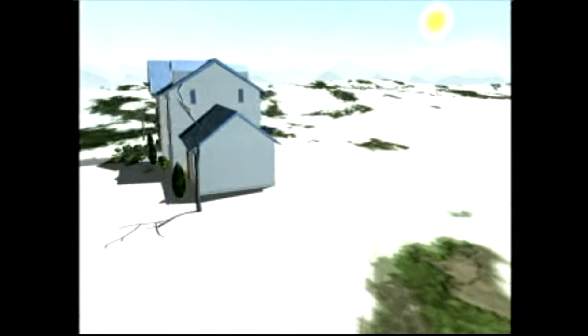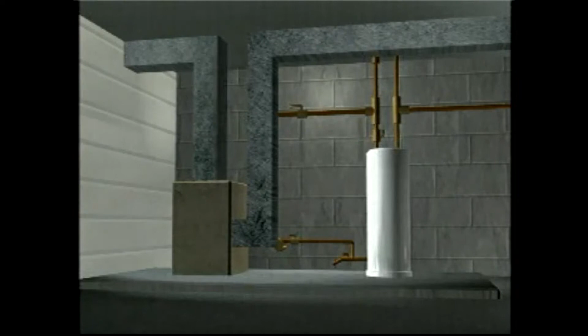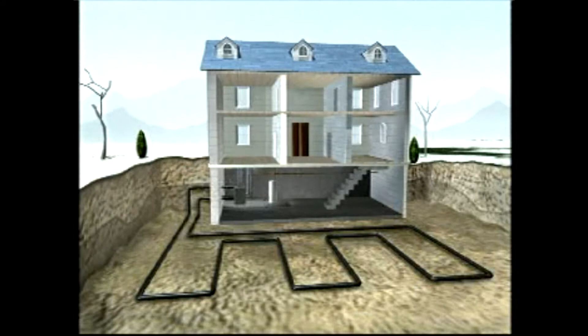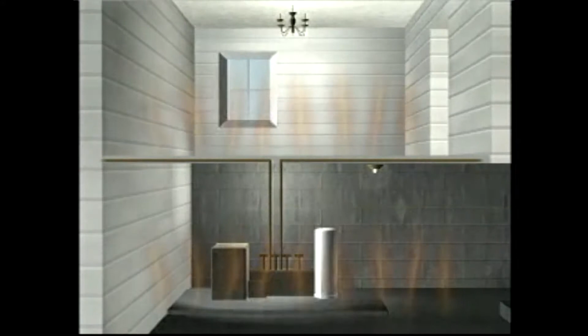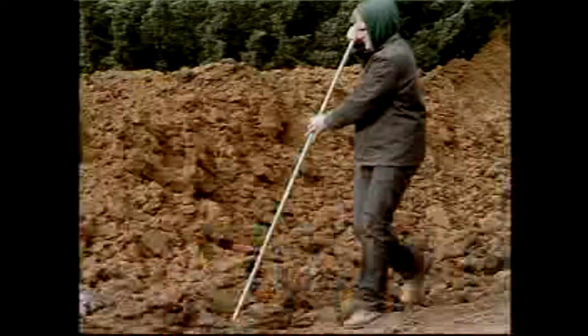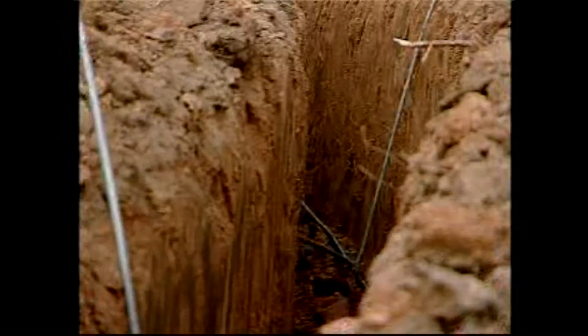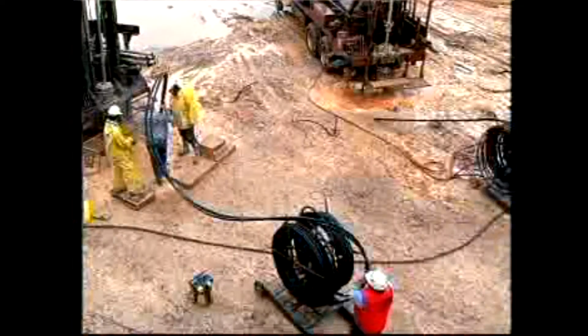A geoexchange system is made up of 3 components: a heat pump, usually located inside the building where it's protected from the environment and vandalism; an underground heat exchanger to act as a heat sink to store energy in the earth when cooling, and to extract energy from the earth when heating; and a distribution system, such as air ducts or hydronic radiant floor tubing, to provide comfort control for the building space. The two types of heat exchangers commonly used are open loop and closed loop.